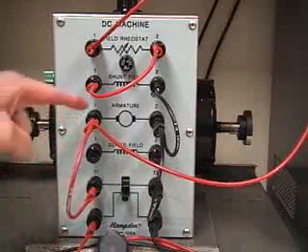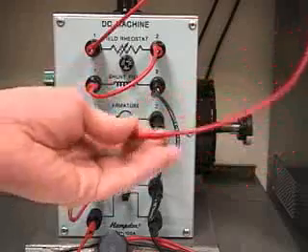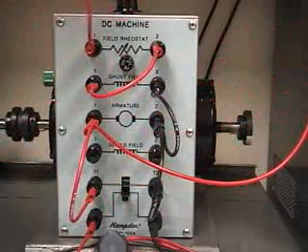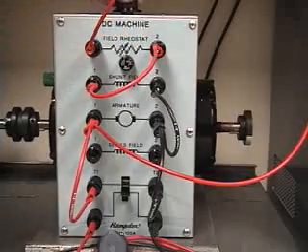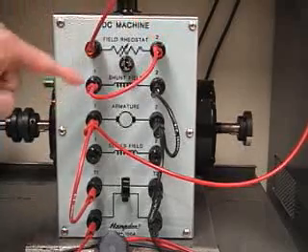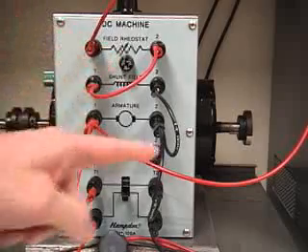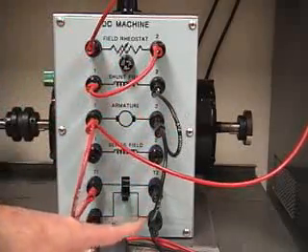The positive input is routed to the armature and that is also going to an ammeter to measure the current and coming back from the ammeter to the field circuit where it's run through a field rheostat, a variable resistor adjusted on top here, and that is in series with the actual shunt field winding that's wound on the stator of the machine. Through the shunt field winding we complete the negative circuit path to the armature and back to the source.